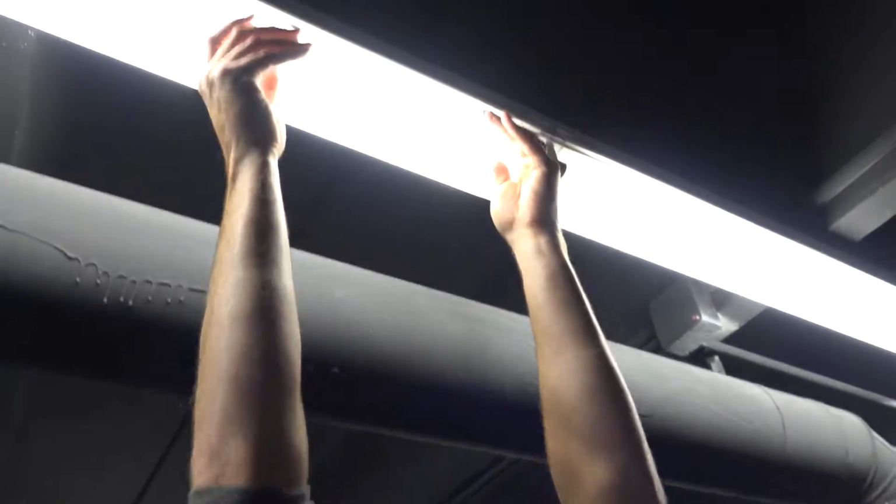Okay, so here we are. Step one is going to be to cut power to the fixture, which I'm not going to do right now because we've got a quick connect in there, so I can take the bulbs out and disconnect power without having to cut a live wire. So first step, take the bulbs out.